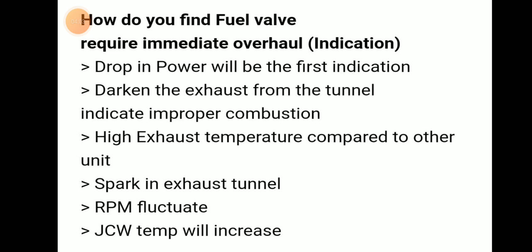First will be a drop in power, meaning speed will get reduced. Then darkened exhaust from the funnel indicates improper combustion. High exhaust temperature compared to other units. Sparks in the exhaust funnel. Then RPM will fluctuate, and jacket cooling water temperature will rise.